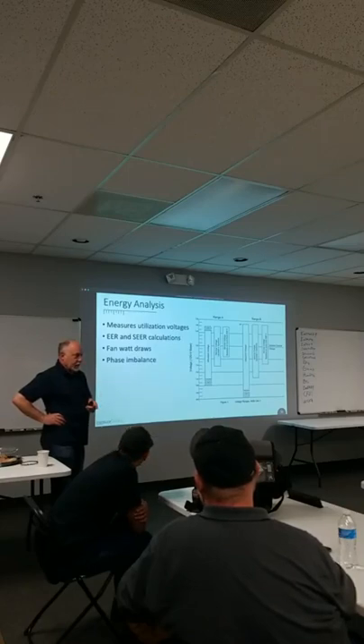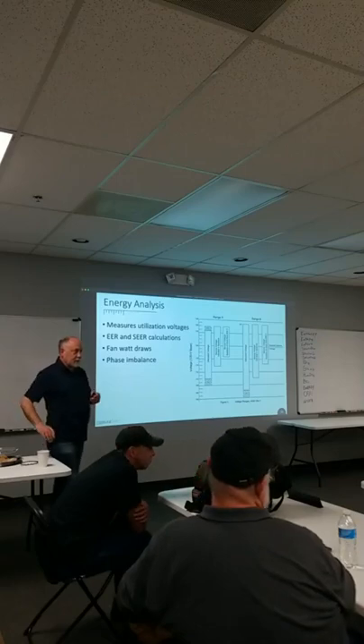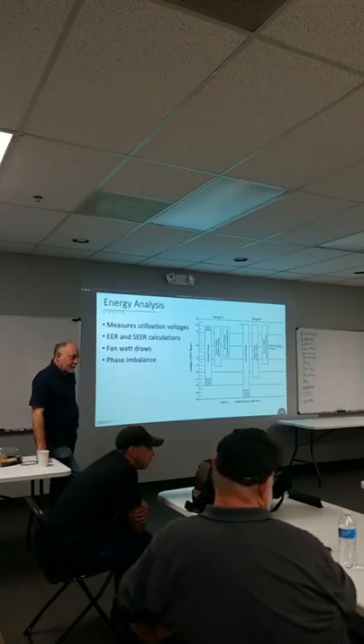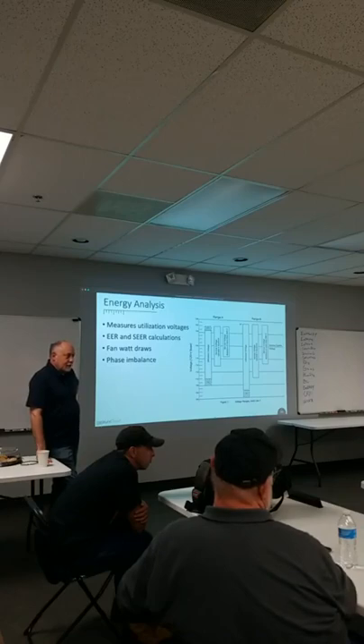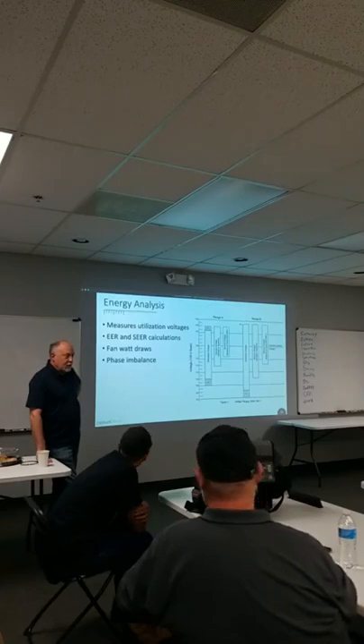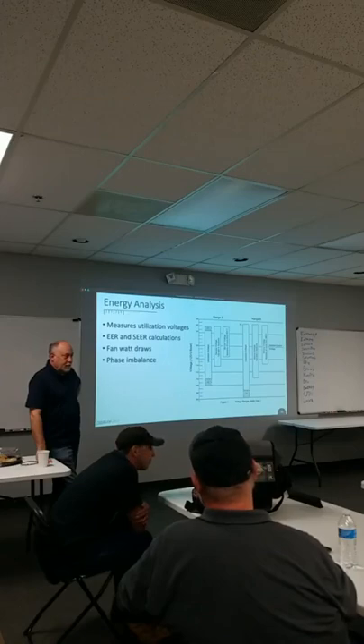In that lab, I've got a 100-foot cord, a 50-foot cord, and a 25-foot cord, and I hooked it up to a table saw. The voltage dropped down to 69 volts, and then it went back up to 95. If I would run this table saw all day long on a 175-foot cord, it would be running at 95 volts and overheat the motor like you wouldn't believe.